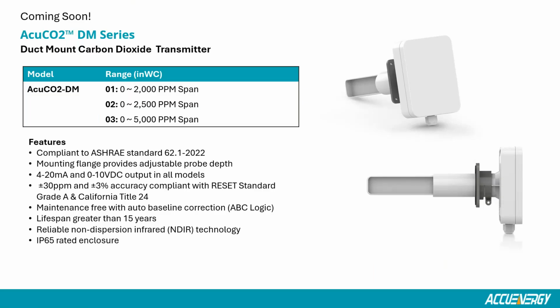Okay, I'm going to keep going here on some of our exciting upcoming product launches. The first one is our ACUCO2 DM series. This is going to be our duct mount carbon dioxide transmitter. This unit is going to be compliant to the ASHRAE standard 62.1. Let me get to the SKU part selection first. It's going to be ACUCO2-DM, and then we'll have the different CO2 ranges. So 01 is 0 to 2,000, 02 is 0 to 2,500, 03 is 0 to 5,000. Probably the most common is going to be the 0 to 2,500 because it does comply with that ASHRAE standard I mentioned earlier, where you have the higher accuracy up to 2,500 ppm.